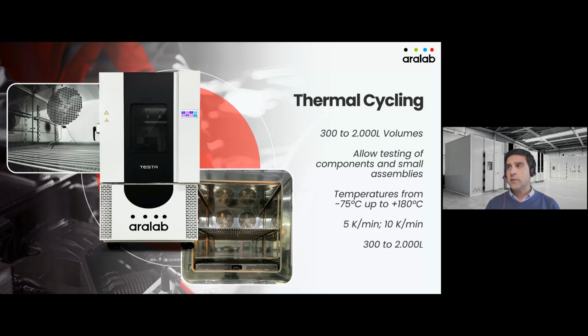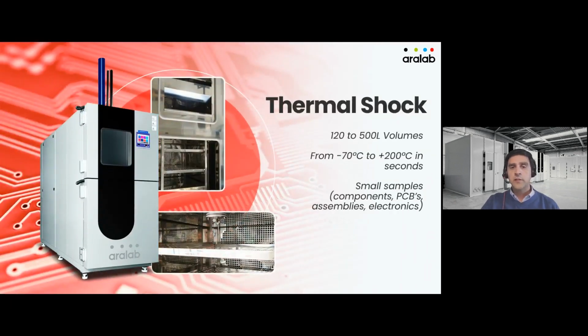So in thermal cycling, again, small to medium components. The temperatures I've already mentioned, people usually start from -75 all the way up to +180. Several speeds available. These are the standards, but upon request, of course, several different speeds may be available, and the volumes that I've addressed. So this was thermal cycling.